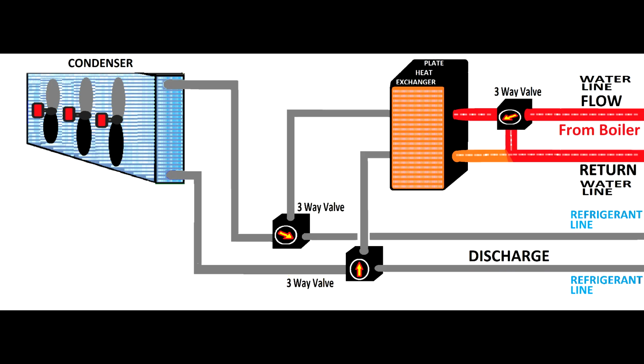If we come across a very cold winter and the refrigeration equipment doesn't have much demand, we'll have a kind of cold store, but we still want to keep it above the freezing point. Now the boiler, which is in line with the plate heat exchanger, will take on more and more of the duty. And as you will see, the three-way valve will allow a small quantity of hot water to go to the plate heat exchanger, so the water will not ice up inside it, because if it ices up, you will break the inside gaskets and the refrigerant will mix with water.